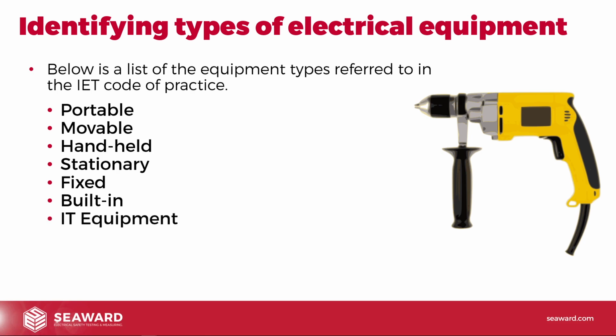IT equipment. Now, generally when people see IT equipment, they think of monitors, PCs, printers, maybe things like that. I tend to use the term electronic equipment, anything that's got electronic circuits, electronic components in there. Again, this generally tends to be pretty low risk equipment, due to what's going on with it and the likelihood of it actually causing injury to somebody. However, it can be quite sensitive. So with IT equipment, electronic equipment, we do need to be careful when we're applying tests to make sure that we don't damage this type of equipment.